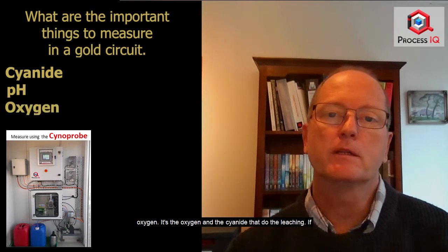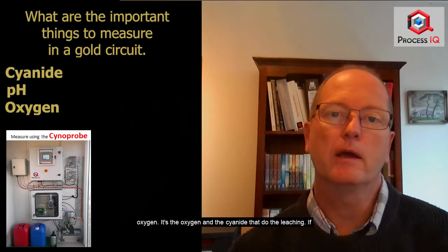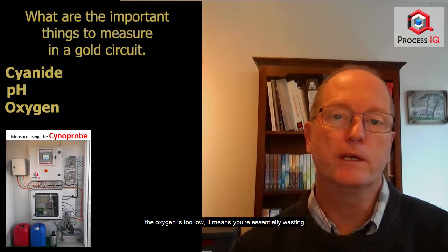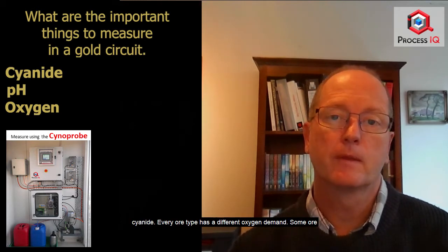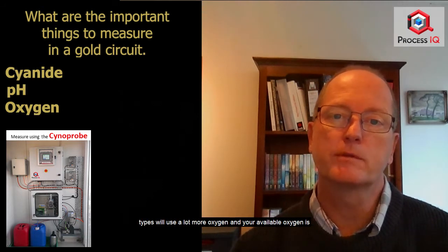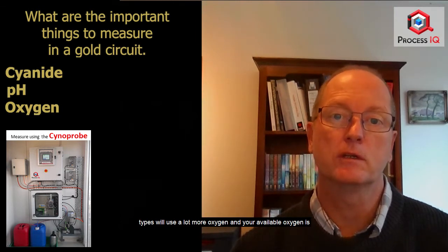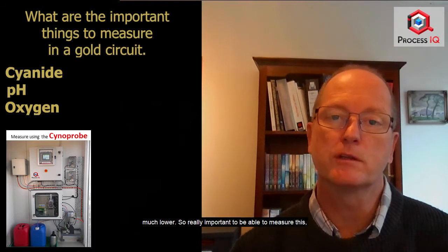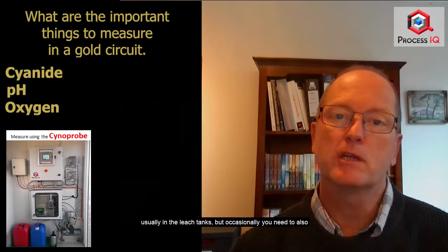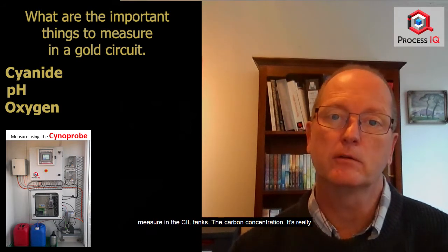The oxygen. It's the oxygen and the cyanide that do the leaching. If the oxygen is too low, it means you're essentially wasting cyanide. Every ore type has a different oxygen demand. Some ore types will use a lot more oxygen and your available oxygen is much lower. So it's really important to be able to measure this, usually in the leach tanks, but occasionally you need to also measure in the CIL tanks.